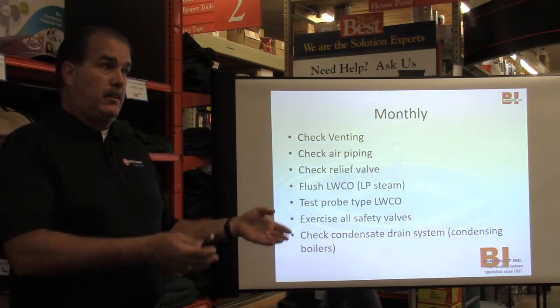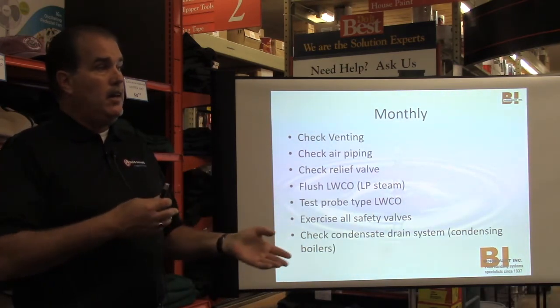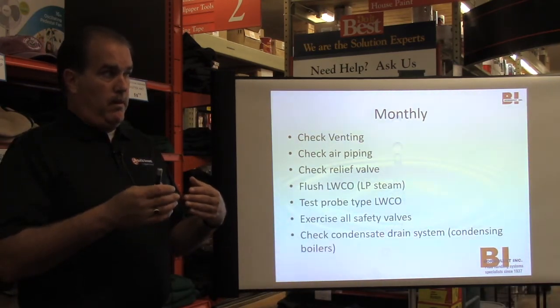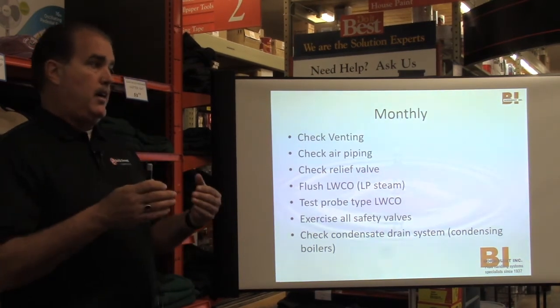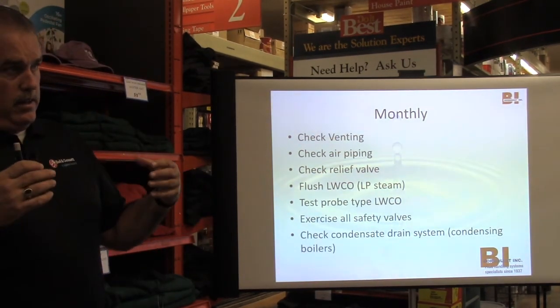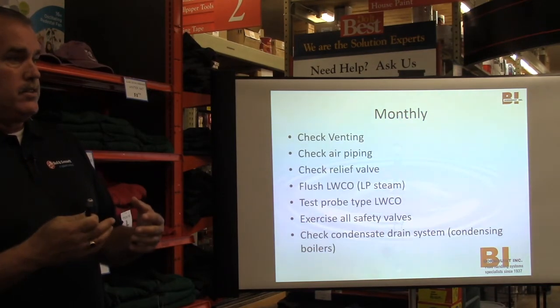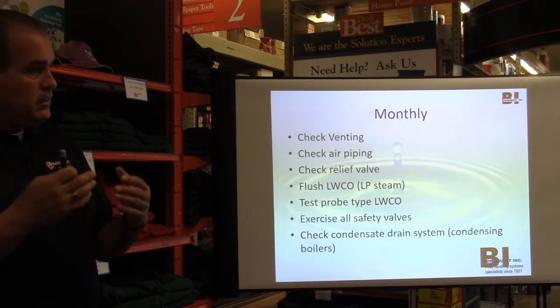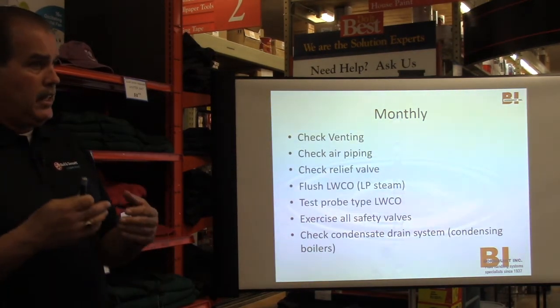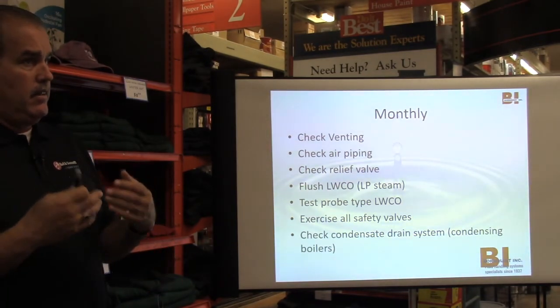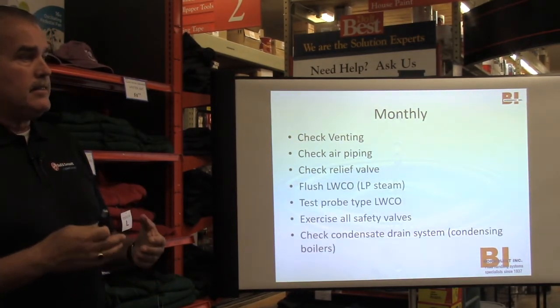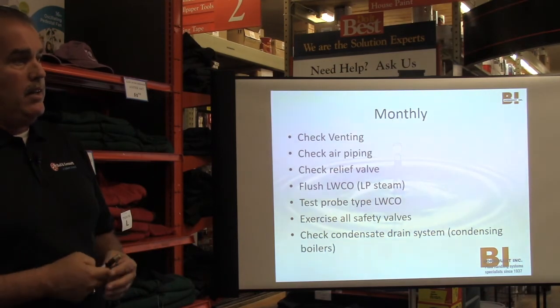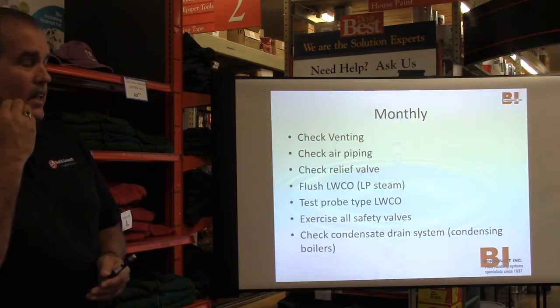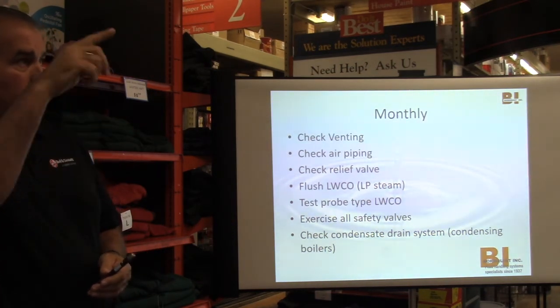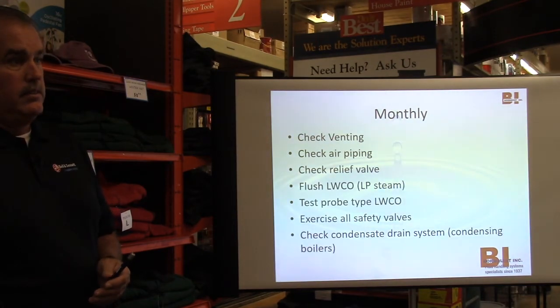Now you're back to the two week cycle or the one week cycle, depending, because you do have to understand that over time, unless you have some source of dirt getting into the system, it should start clearing out. It shouldn't keep constantly having to be done. If you constantly have to do that all the time, you've got a pretty dirty system, and that dirt's not only going to get in the boiler, it's going to get other places and cause you fits.